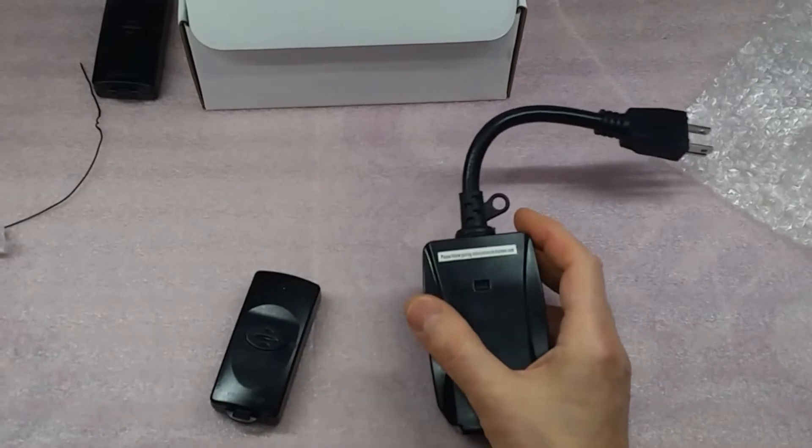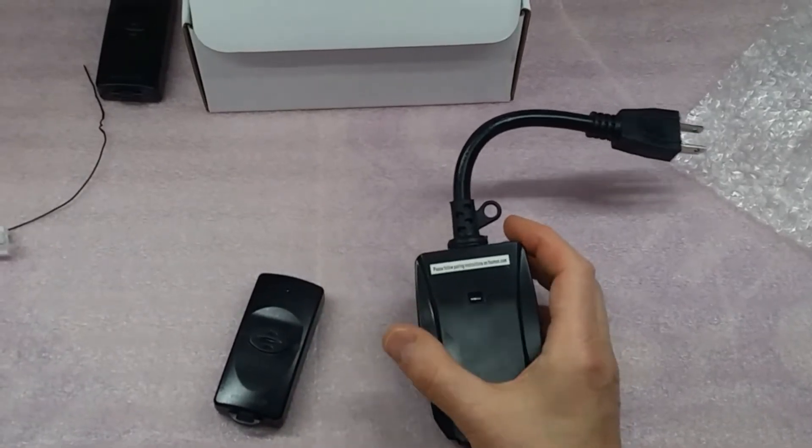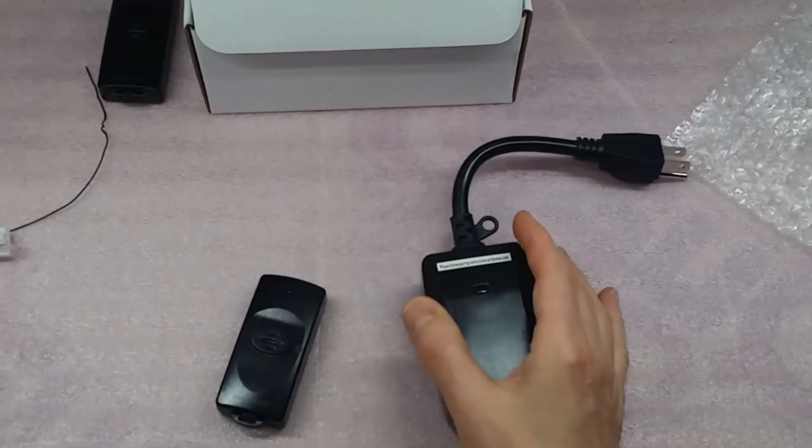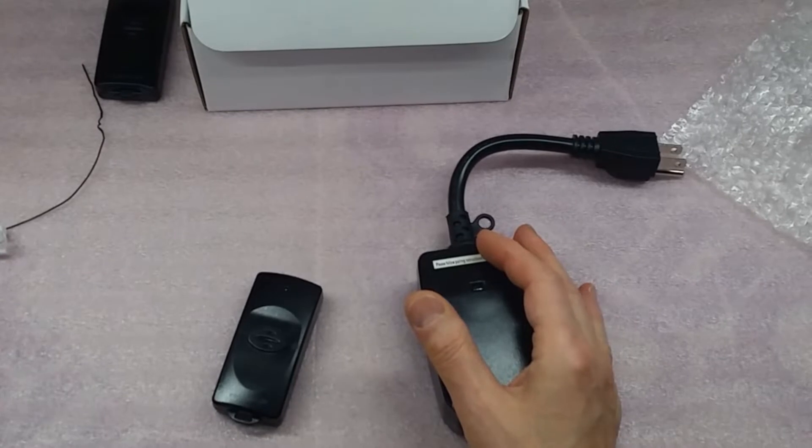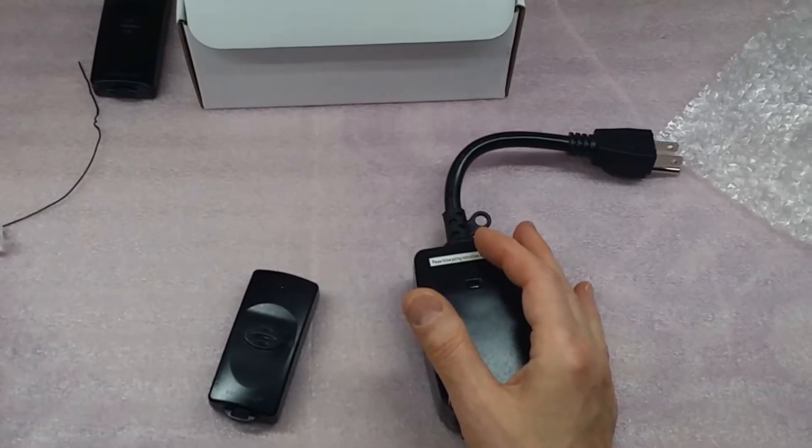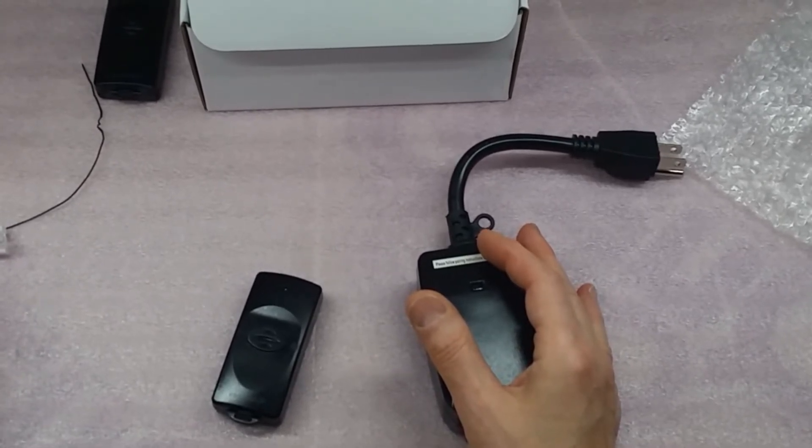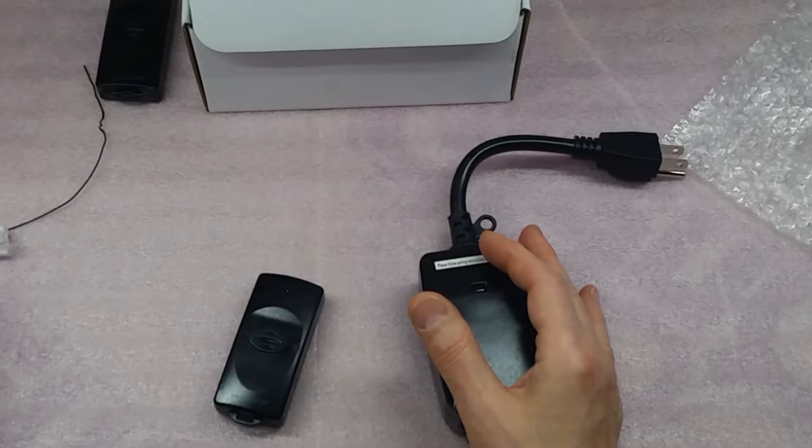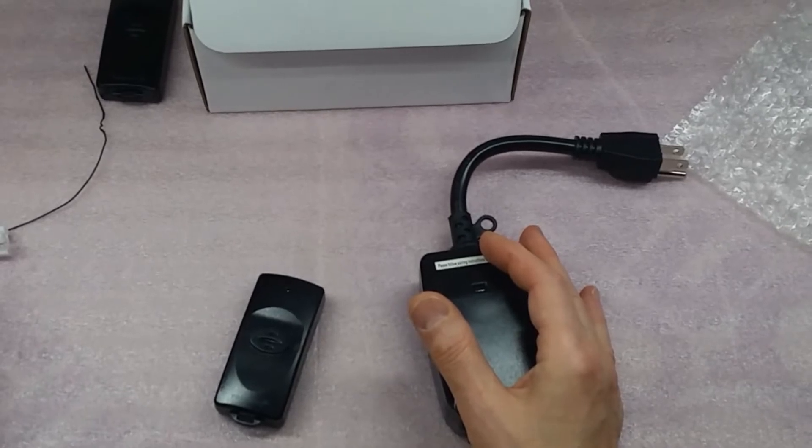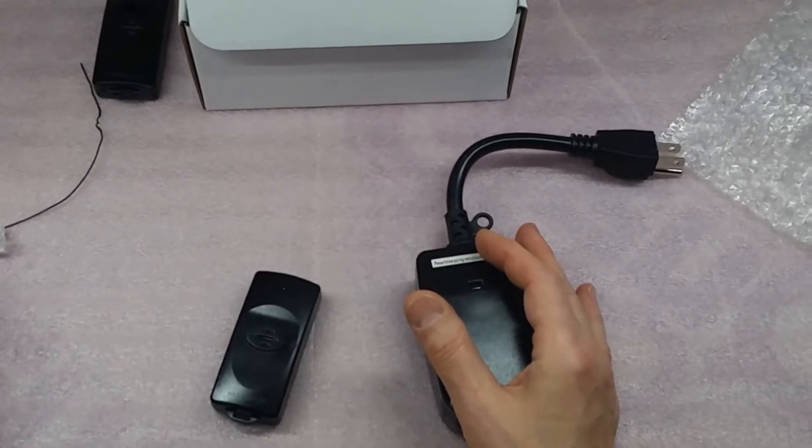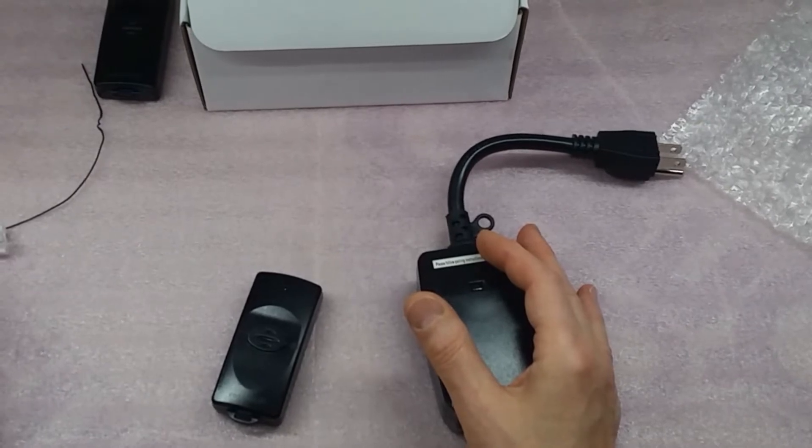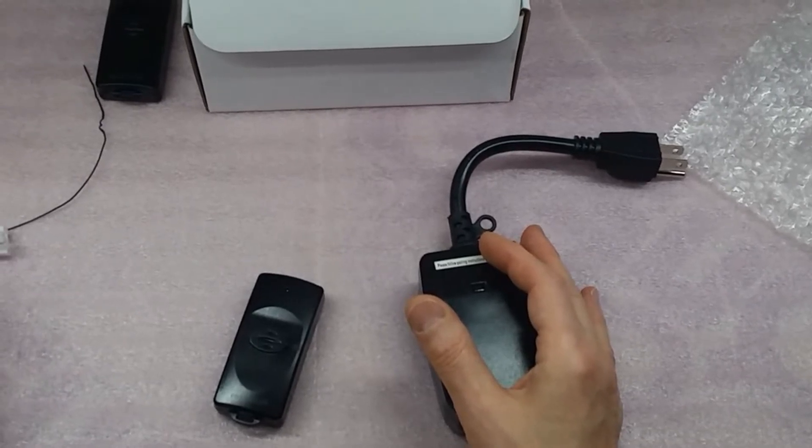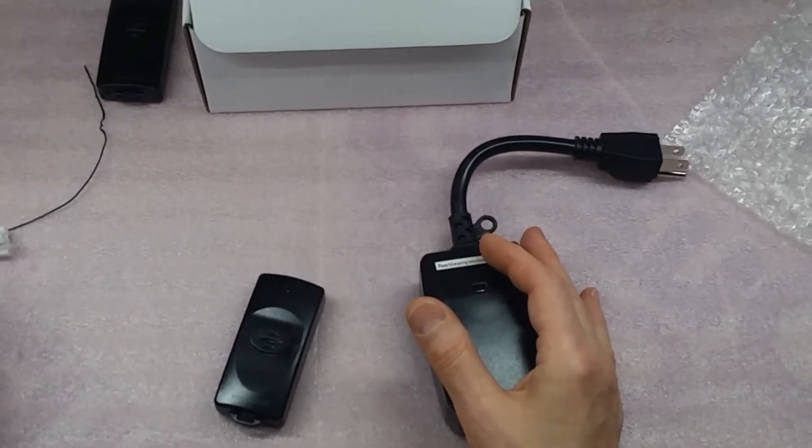It's rated for 125 volts, 15 amps resistive load, 15 amps for general purpose load, 10 amps for tungsten, 1250 watts, or a half a horse at 125 volts.